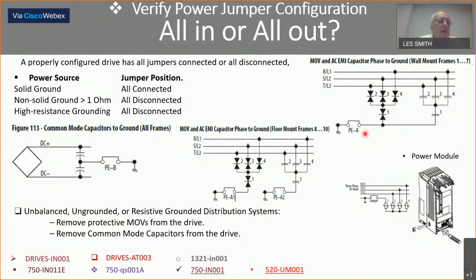What does it just read here? A properly configured drive has all jumpers connected or disconnected. Solid ground, all in. Non-solid ground, greater than 1 ohm, all disconnected, or high resistance, all disconnected. And you see various wiring diagrams. PEA and PEB are what we're going to see in our drives up to about 400 horsepower.